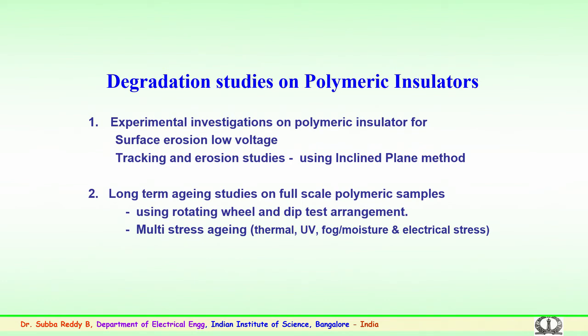Further to that, long term aging studies are very important on full scale polymeric insulator samples. This long term aging is normally conducted either using a pollution chamber where salt fog is continuously sprayed on the sample and the voltage is applied continuously for 1000 hours. That is one experiment. The second is the use of a rotating wheel and dip test arrangement, a very important experimental facility that has to be created, where the wheel rotates at a specified time, and during the process the insulator dips in the contamination. It has 4 phases where it has to cross to the high voltage.